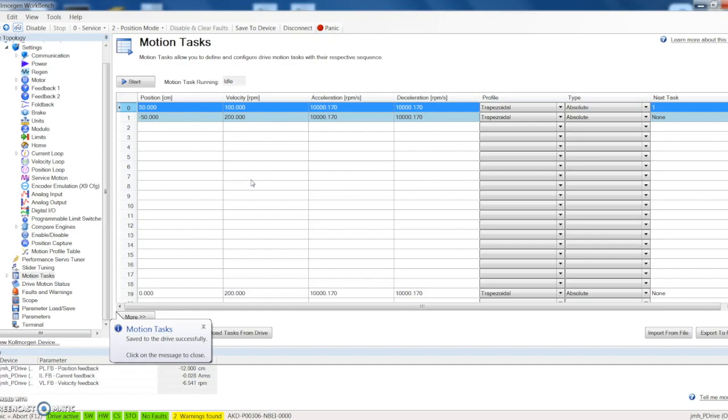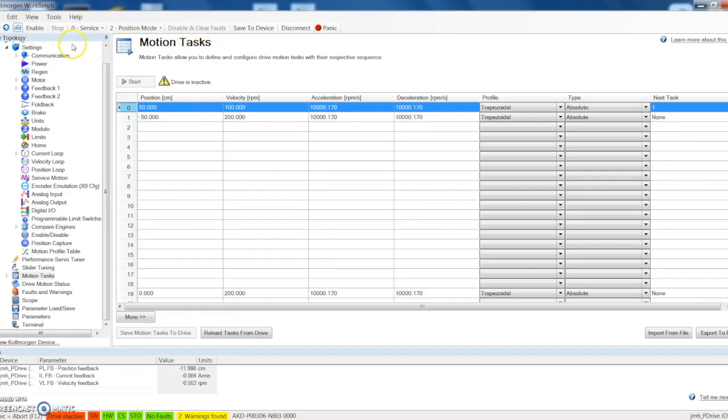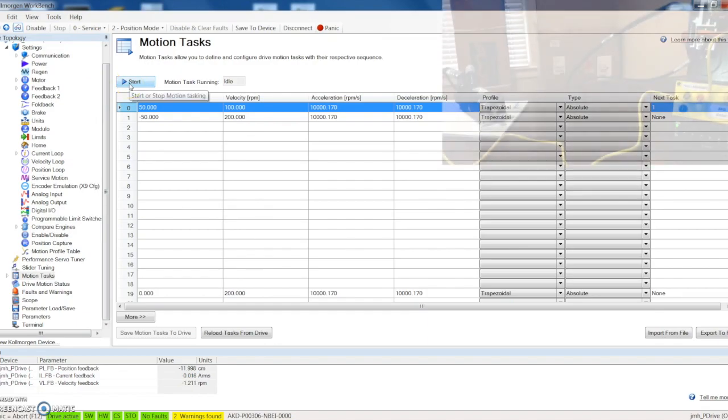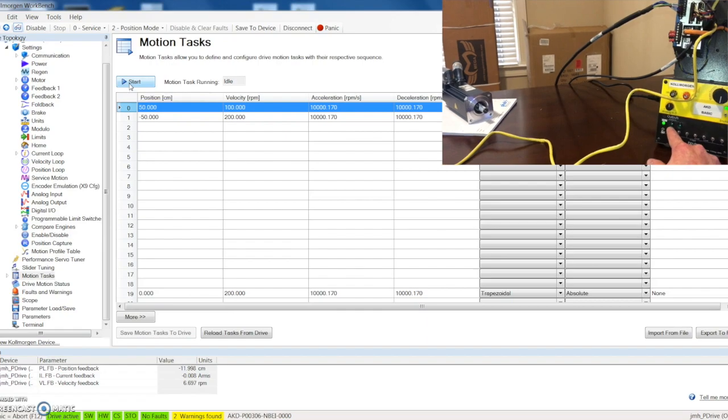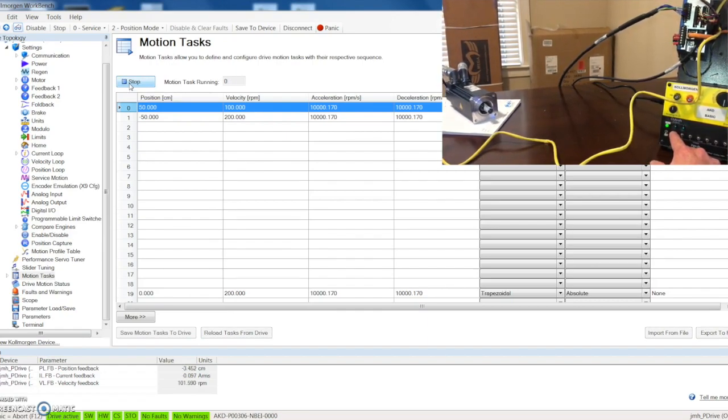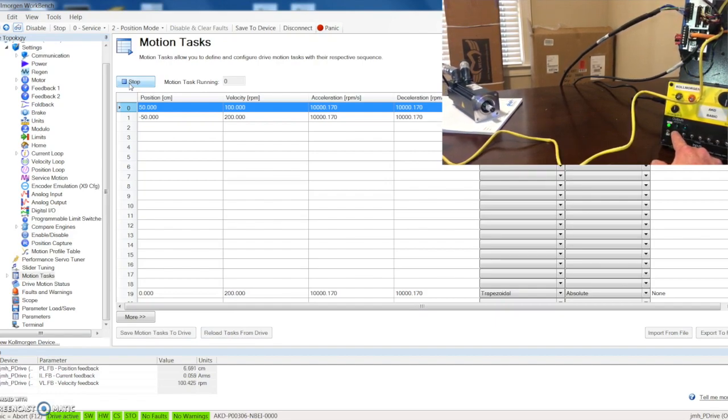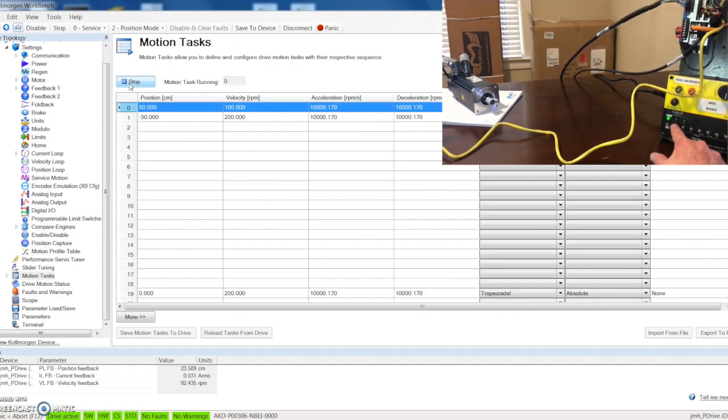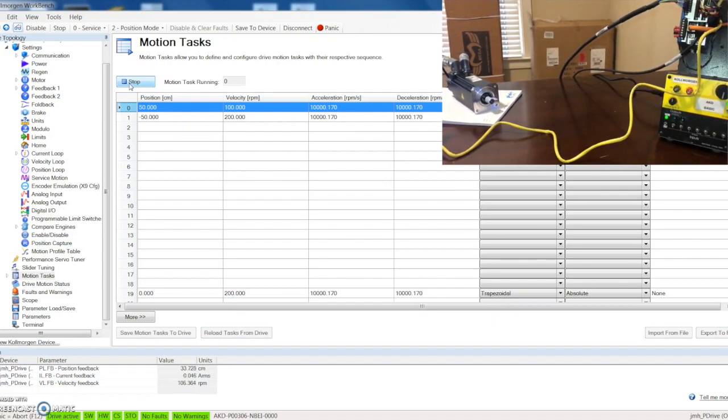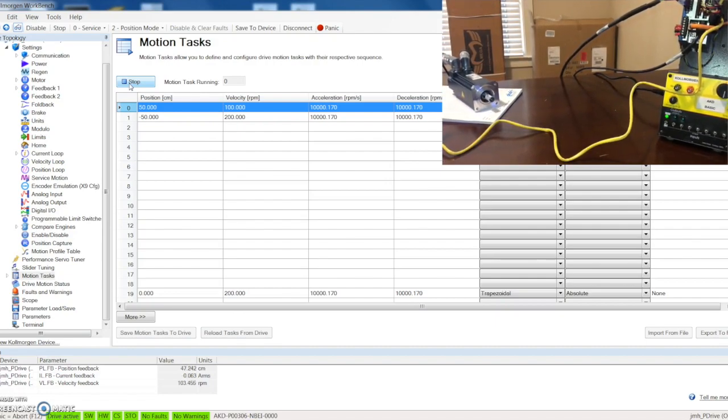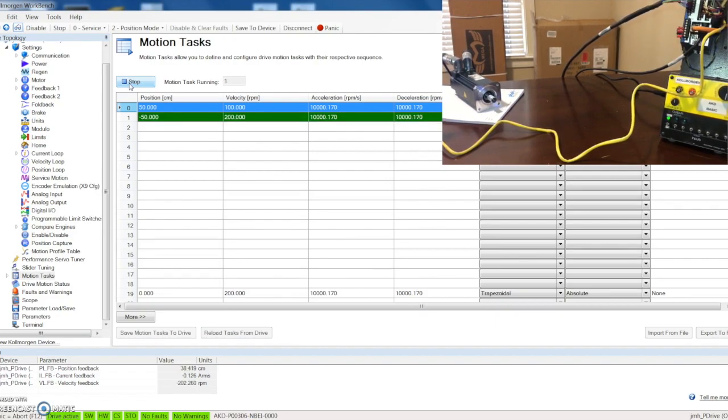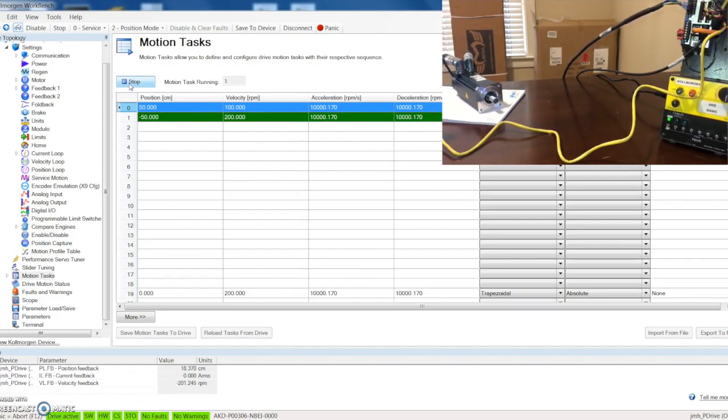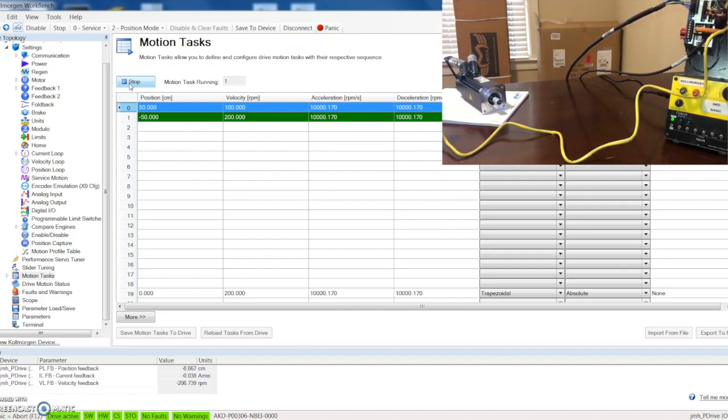And have it move. So let's see what that looks like. First let's disable, enable. Let's start this move and let's trigger it off of our input. Okay, so it's going out to 50 centimeters which essentially should be 10 rotations. And when it gets there it's going to stop, it's going to hesitate for 500 milliseconds, and then it is going to go reverse in the opposite direction. There it's gone. It's going faster because we set the RPM to 200, twice the speed of the forward motion. And when it gets there it's going to stop.